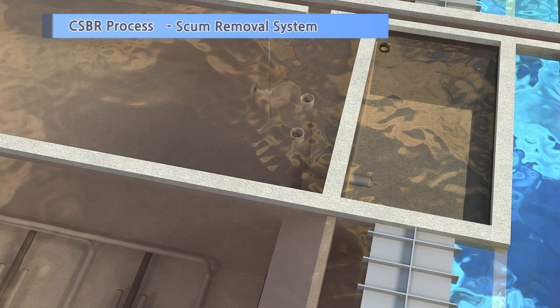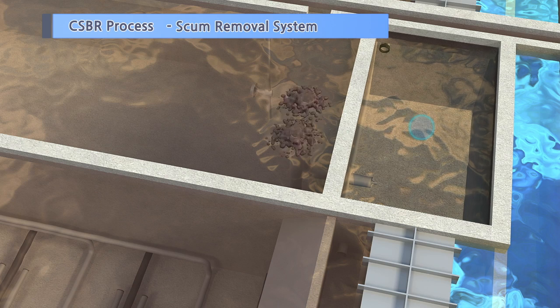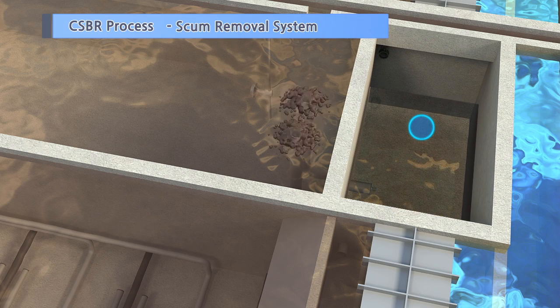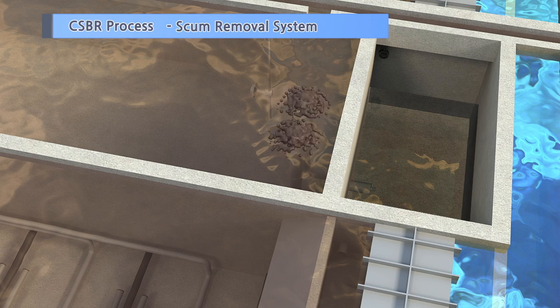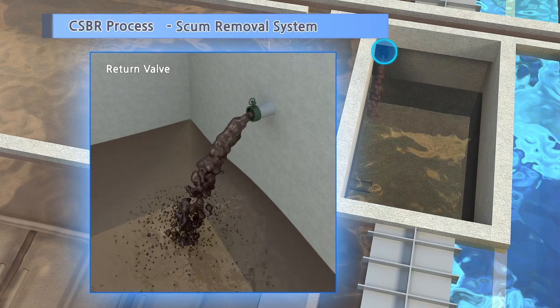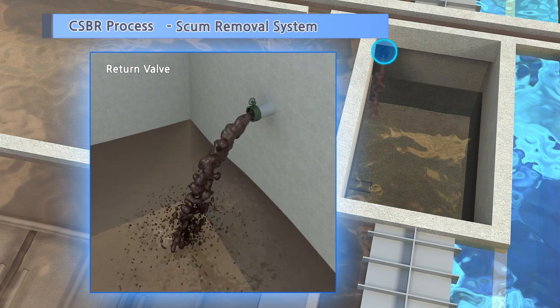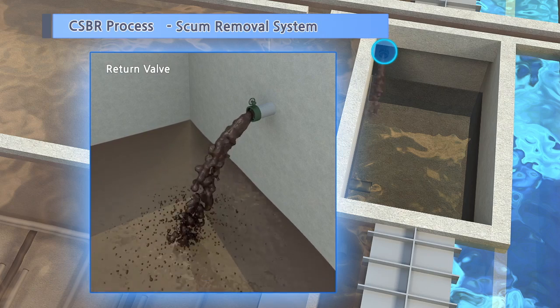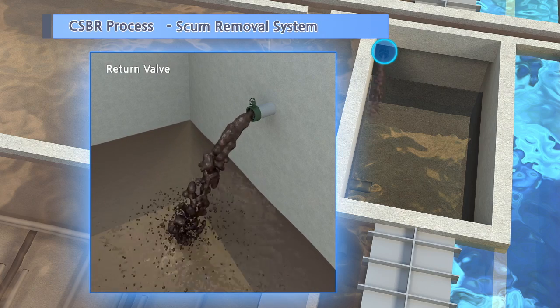The scums and bubbles that were created in each cell during operation will finally end up in the SBR cells due to gravity flow. Before the return process begins, the operating pump drains the RAS chamber to lower the water level. Next, the valve opens and the return process starts. The return water flows like a waterfall, ramming hard against the RAS chamber, in which the scum is broken.